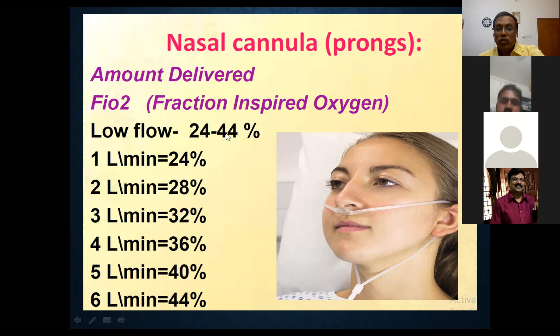So with a low flow device, we cannot increase this more than 6 liters. If we add more than 6 liters, it is very uncomfortable for the patient, and the patient cannot tolerate this cannula. The maximum FiO2 delivered for room air is 21%. From 1 liter to 6 liters, it delivers an FiO2 of 24 to 44% to the patient.